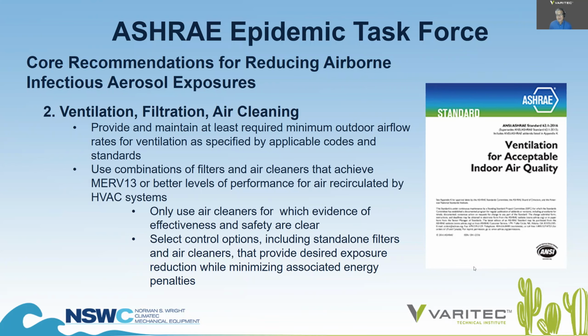And that's a consideration with your system. As many of you are aware, if you enhance your filtration, you will increase your system static pressure to your air handler, providing air to a building. You need to evaluate whether or not the horsepower and fan sizing of those units are enough to overcome the added static pressure that results from this enhanced filtration.